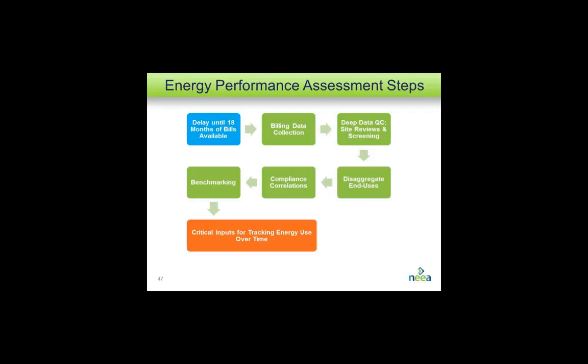We determined the total EUIs for each of those buildings, then used a tool called EasySim to disaggregate the end uses. The approach is essentially a straight change point analysis to disaggregate the heating and HVAC loads, using characteristics gathered from the buildings, such as the LPD and the UA, to disaggregate other end uses. Then we take both the total EUIs and the disaggregated end use EUIs and correlate those with the compliance determination for these buildings for each system, so we have the EUIs for each major end use, and the compliance for each major end use.